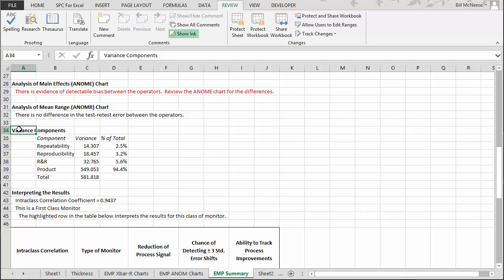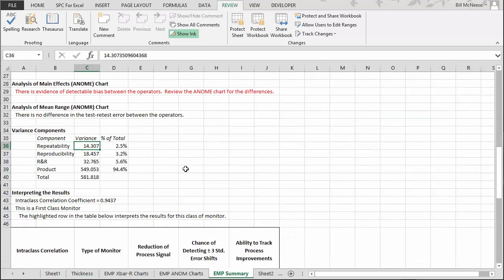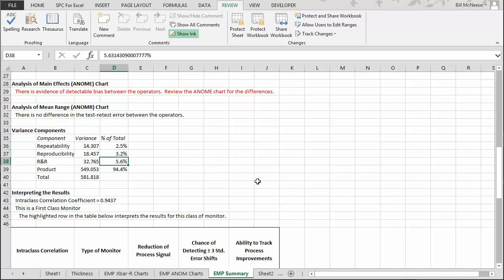Now we'll move on to the variance components table, which lists each component, its variance, and the percent of total variance due to that component. Repeatability, calculated from the average range on the R chart, is 14.3. Reproducibility, based on the range of averages across operators from the main effects table, is 18.457. The combined gauge R&R is simply the sum of these two. Product variance and total variance are also calculated. Repeatability accounts for 2.5% of variance, reproducibility 3.2%, combined gauge R&R is 5.6%, and product variance is 94.4%.